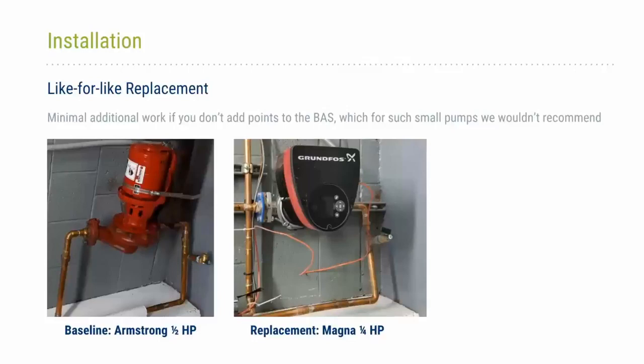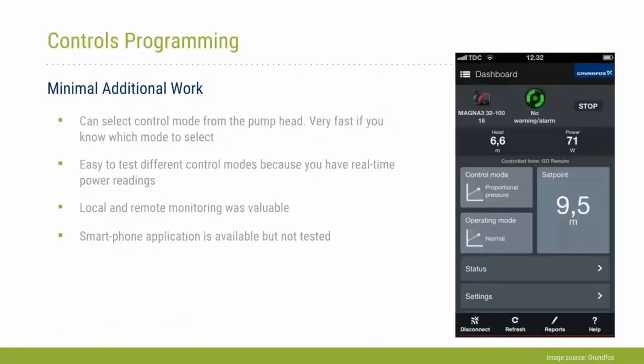One of the things that was convenient with these pumps is they have easily swappable communication cards. For the purposes of this study, we used Modbus cards to send NREL the respective data that they needed from the internal pump sensors. Once that initial data evaluation was completed with NREL, we were able to pull out those Modbus cards and switch in new BACnet cards to allow for integration into our BAS and pull those points out of the system. Next slide.